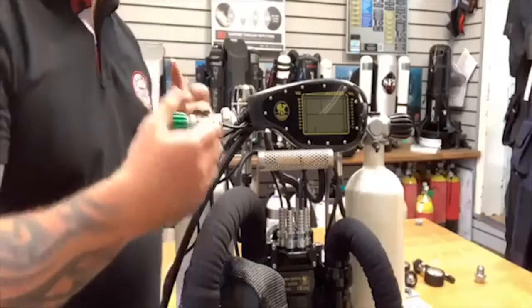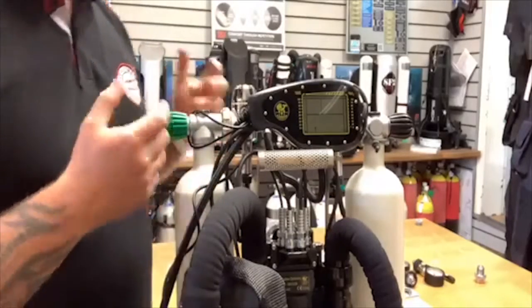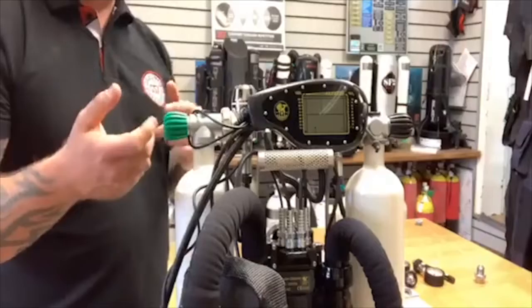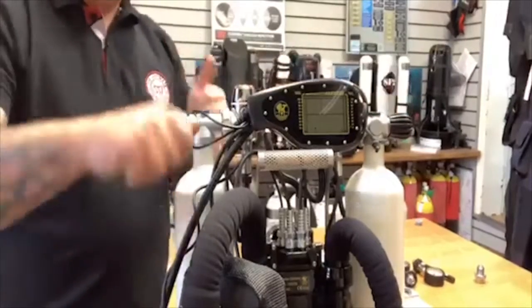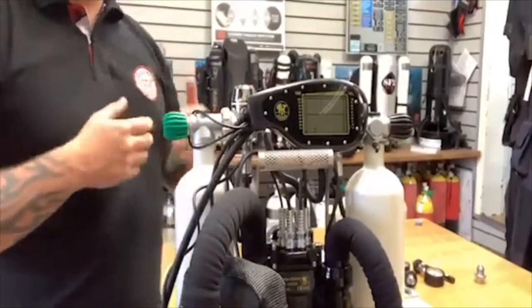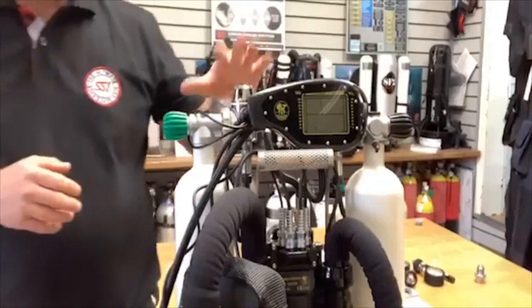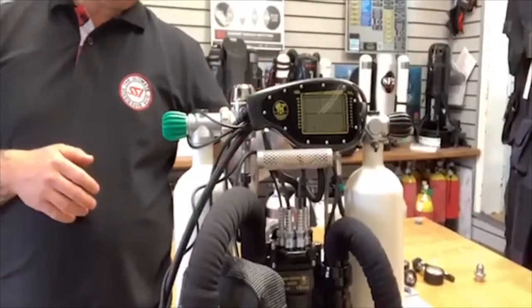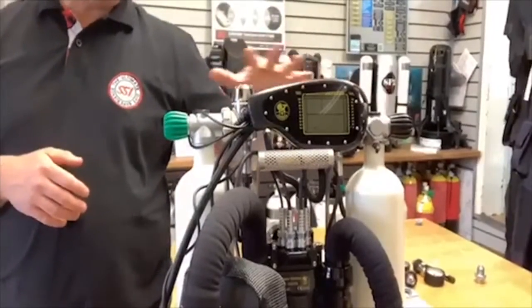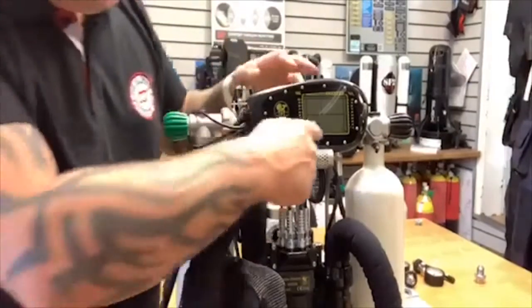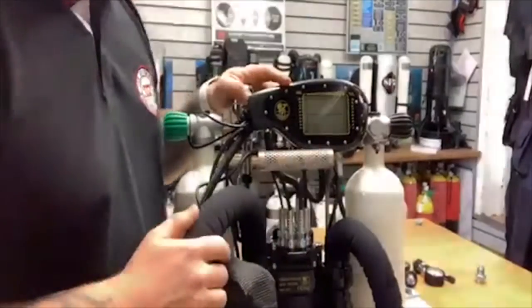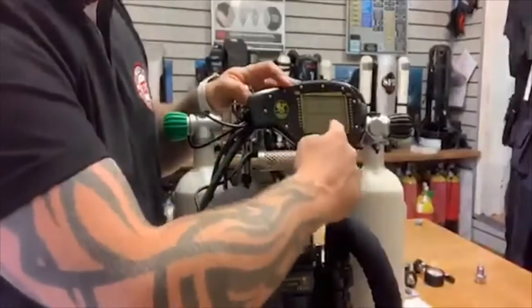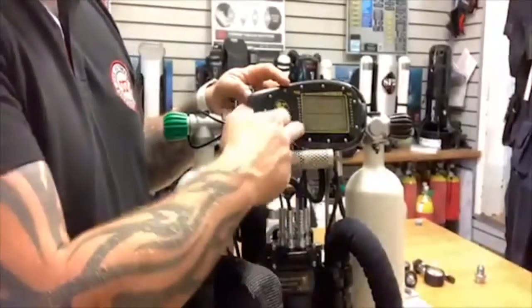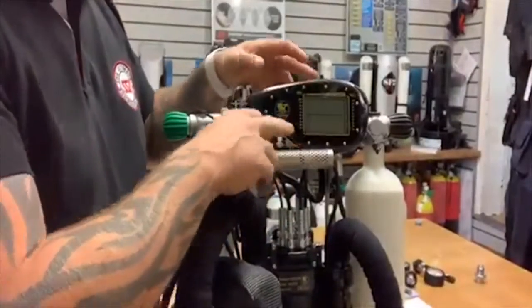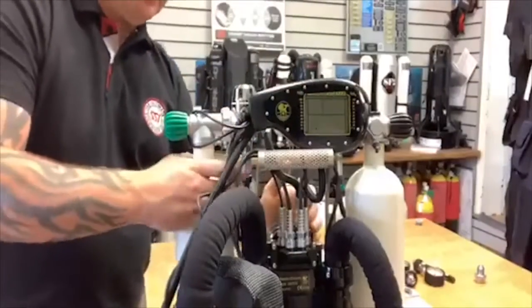It'll then ask us to manually step in from time to time. You'll hear it beep and say, please step in. It might ask me to open the cylinder valves, to change the mouthpiece position, and it's going to go through its startup check. One of those checks is to calibrate, and during its calibration process, it'll also confirm that I've got the gases that I said I'd have. On the one side here, you'll see the test number. If it fails, over on the other side, you'll see the failure number. So we've got an idea where we are. Let's start the machine, and we'll see how we go.